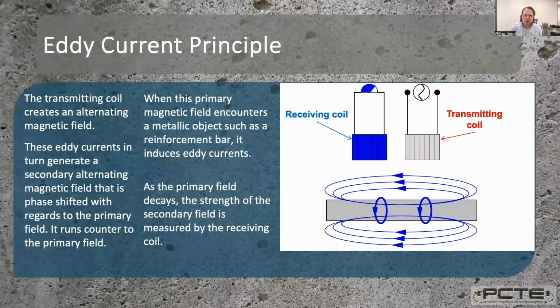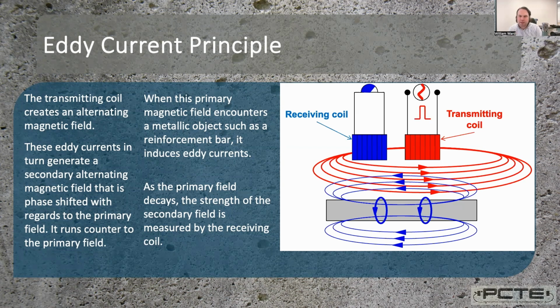The key thing to understand here is at no point did our cover meter record a measurement in units of depth. It's recorded a measurement in units of signal strength. And it's this signal strength that we're going to use along with the calibration process to take depth measurement on site.